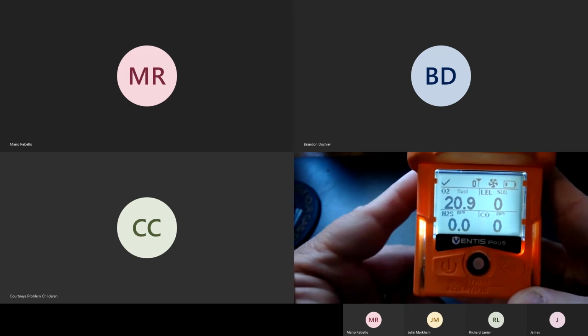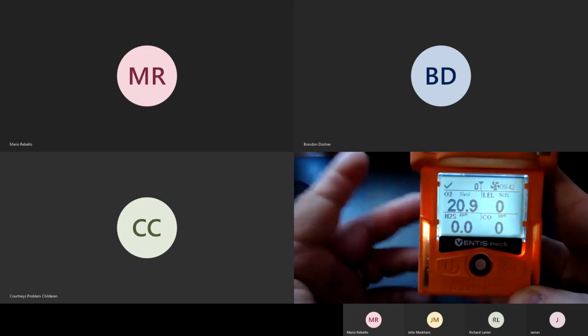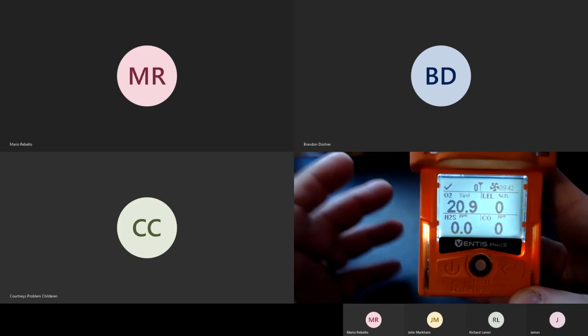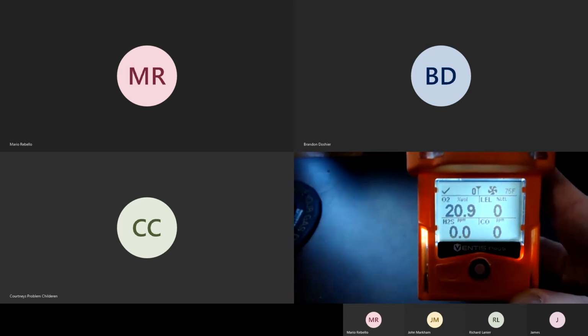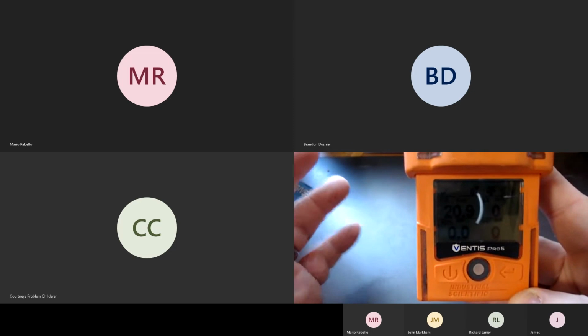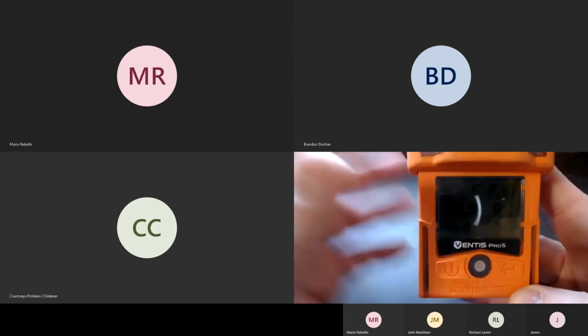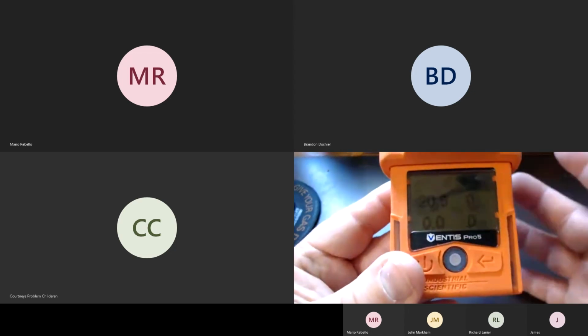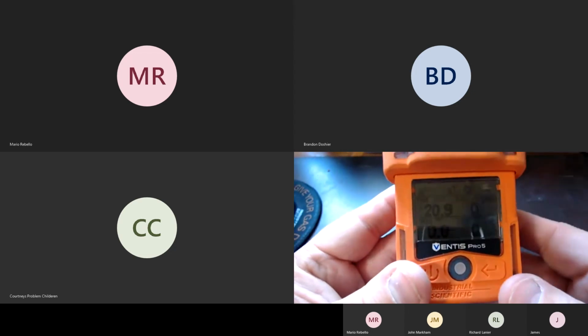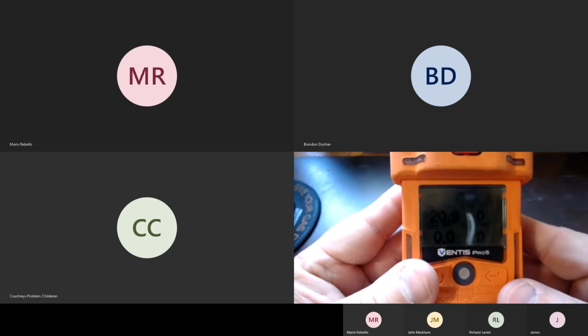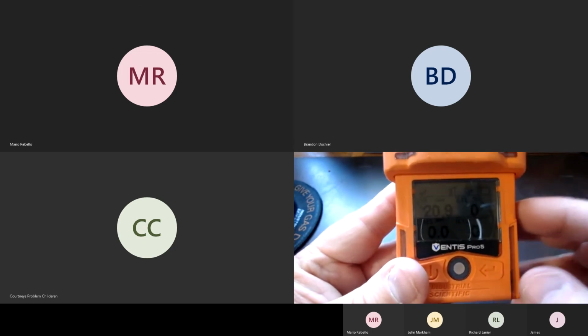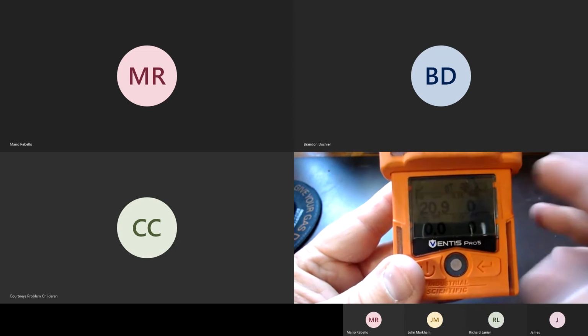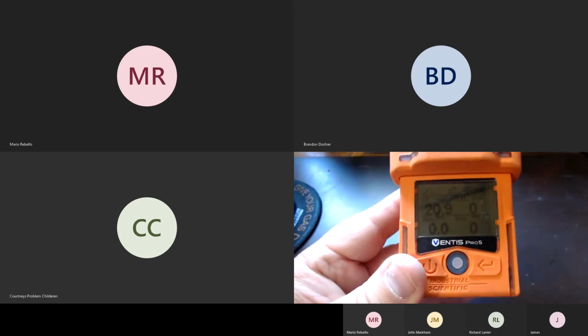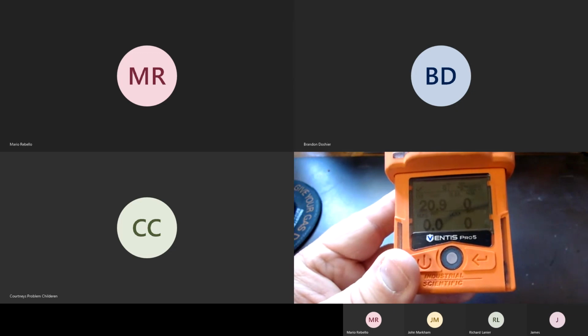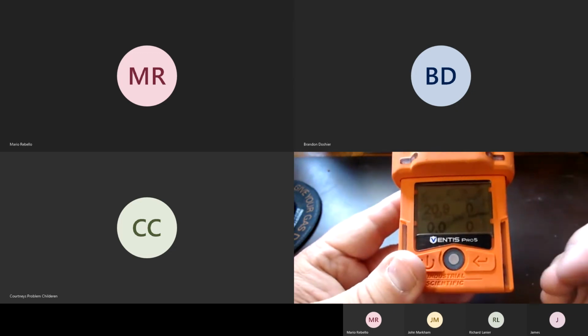All right, so now we're at our real-time display. This is where it becomes very vital to remember a couple of things. Whenever you turn the instrument on, we know to press and hold the power button, it comes on, and we do the pump check. That's a no-brainer. There are a couple other steps we have to do. After you turn it on, you have to do what's called zeroing of the instrument. Zeroing is done in a fresh air environment. You go to the zeroing screen, I'll show you how in a second, and you hit the enter button, and it does a zeroing. It establishes the baseline for the sensors.